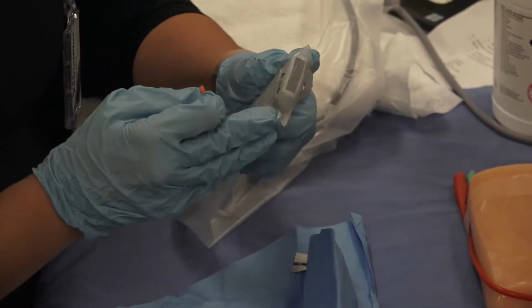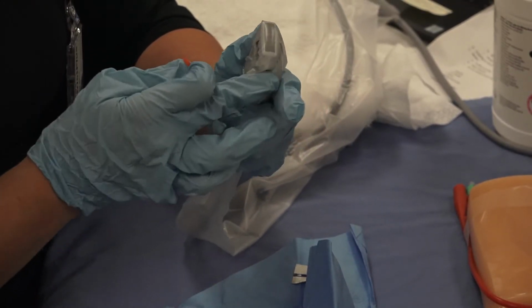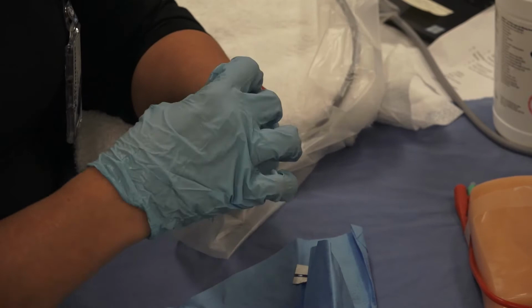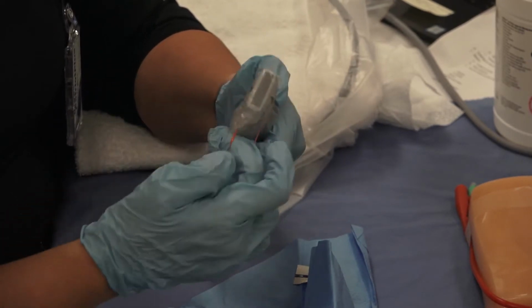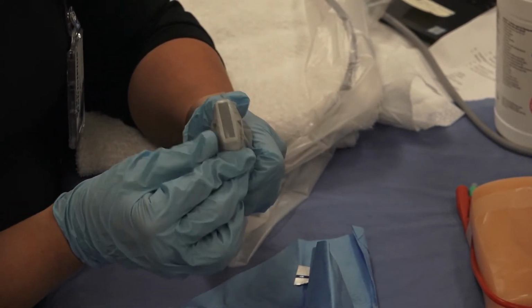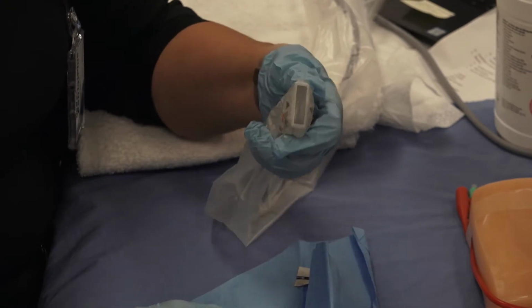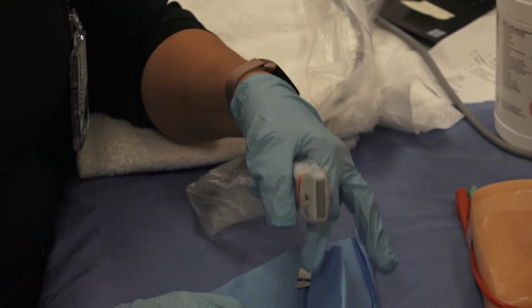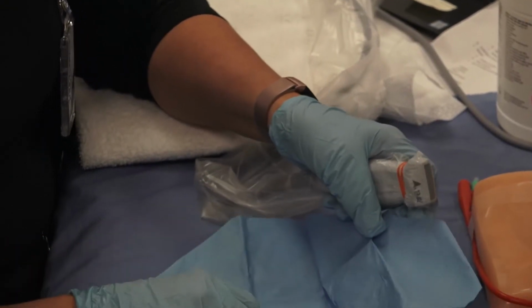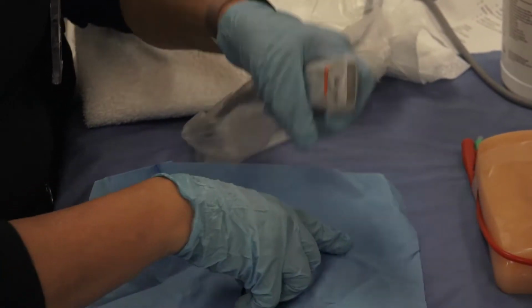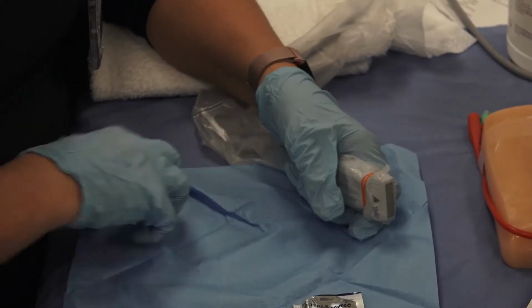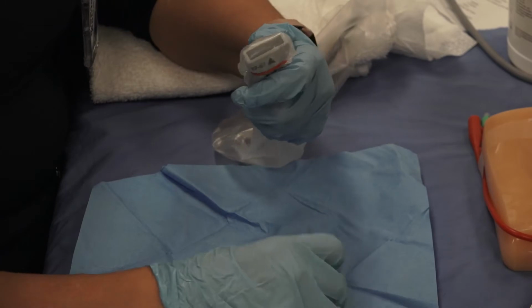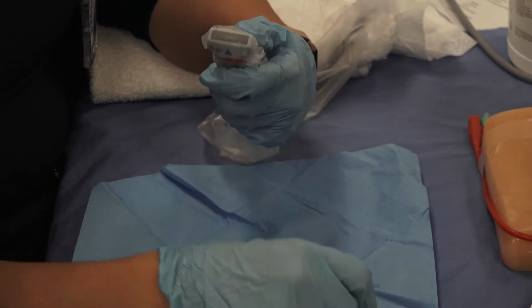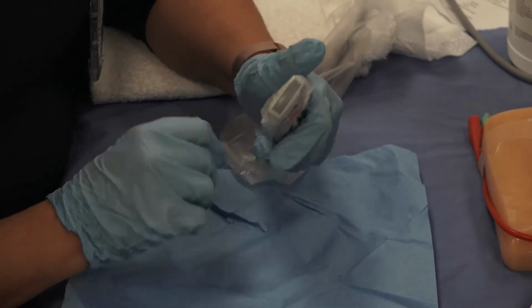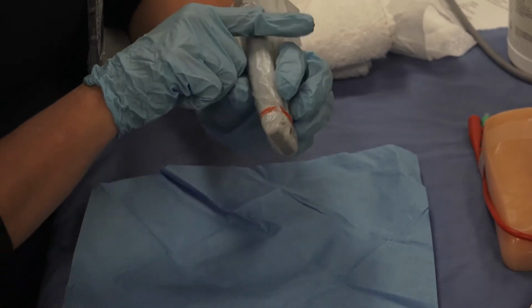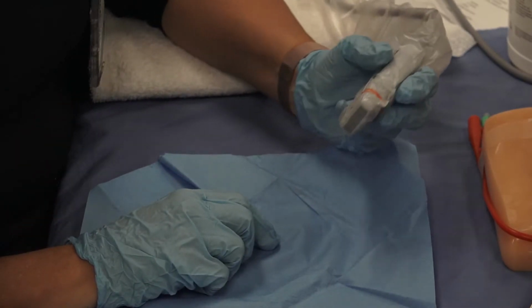Then it's got the rubber bands, and the idea with the rubber bands is to keep a tight contact here so that you don't get a lot of air in the way when using the ultrasound. You can use one or you can use two based on your preference. And then before you use it on the skin, you'll put more ultrasound gel on the top of this. Before I do that though, I want to show you the difference between the views.